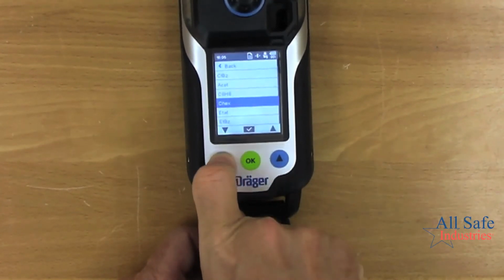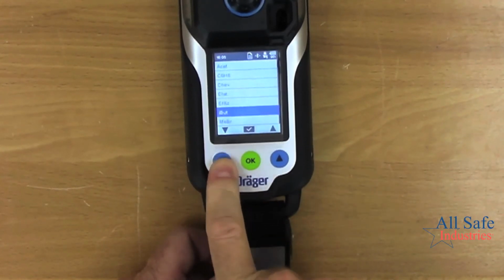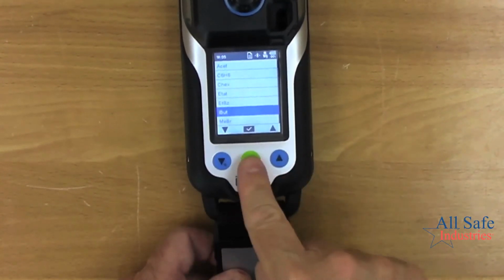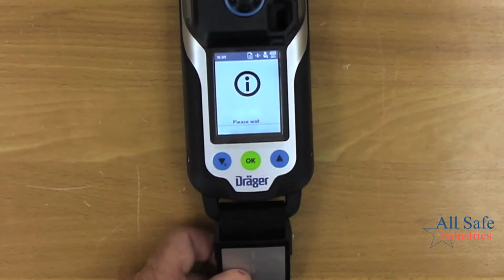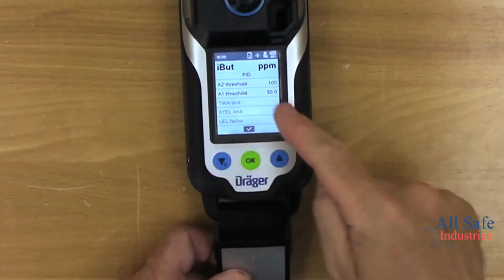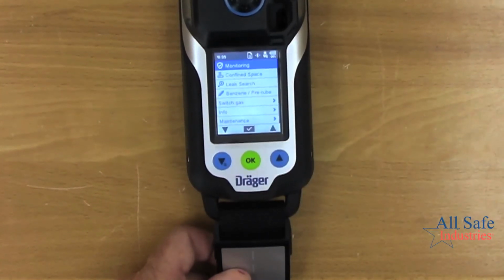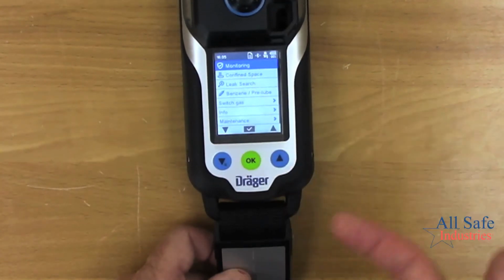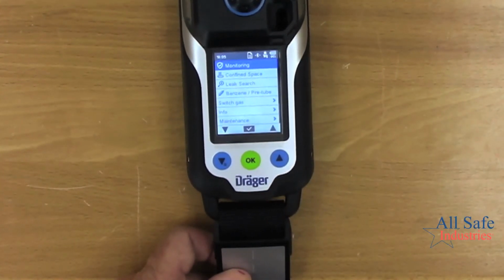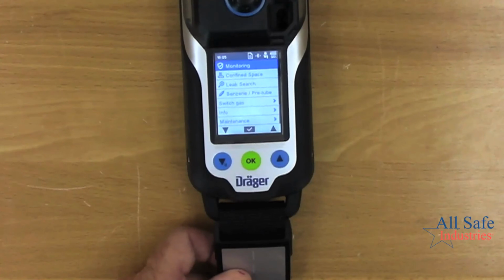You can pull this information off many different apps. There's isobutylene, so if I were to select that it says please wait, and now my PID is set to the correction factor for isobutylene, which is also my calibration gas. So again, lots of things I can do in the menus.